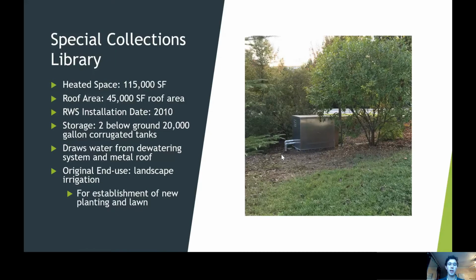There is a rainwater system included in this building, installed at the same time that the building was constructed in 2010. Water is collected from the metal roof and the dewatering system and stored in 2 below ground 20,000 gallon corrugated tanks. The original end use for this system was landscape irrigation. So this was for the establishment of new planting and the green lawn in front of the building. However, since then, the plants have established themselves and the irrigation lines have been severely damaged, so there's no longer possibility of using that same irrigation setup.